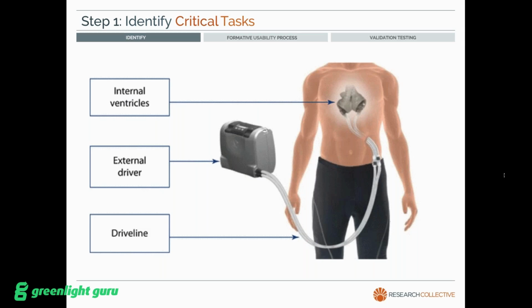Air from this external driver on the left is pumped into the heart through drive lines. In the event that the external driver fails or malfunctions, the patient must be detached from the faulty driver and connected to the new driver. If you're imagining what's happening here, you're probably right. This must be done quickly, because as soon as the drive lines are disconnected from the external driver, the artificial heart stops and the patient's blood stops circulating. So this must be done quickly, it must be done accurately, and it's done under a lot of stress. Like I said, this is a pretty easily identifiable critical task.